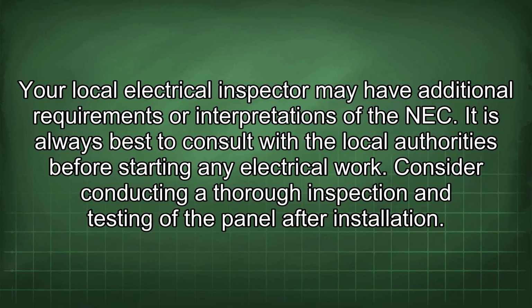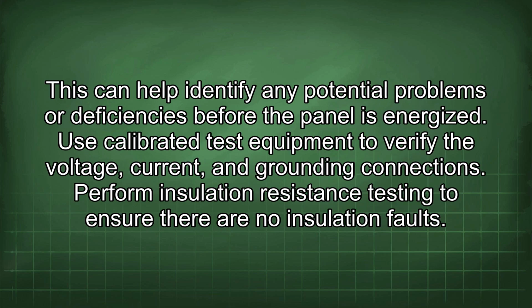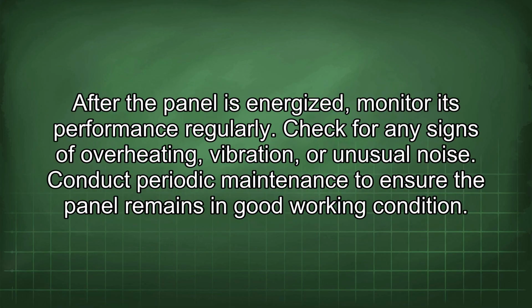Consider conducting a thorough inspection and testing of the panel after installation. This can help identify any potential problems or deficiencies before the panel is energized. Use calibrated test equipment to verify the voltage, current, and grounding connections. Perform insulation resistance testing to ensure there are no insulation faults. After the panel is energized, monitor its performance regularly. Check for any signs of overheating, vibration, or unusual noise.